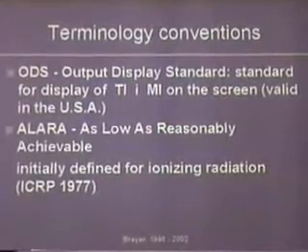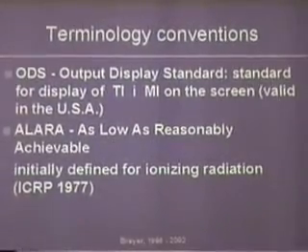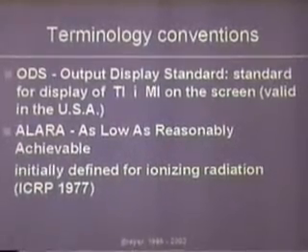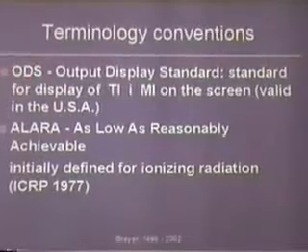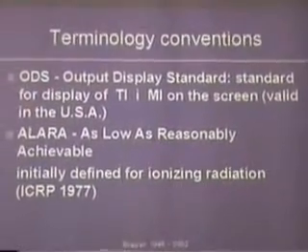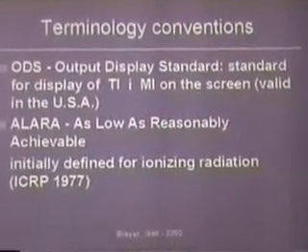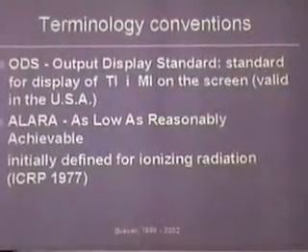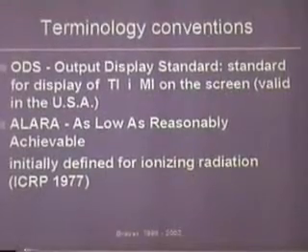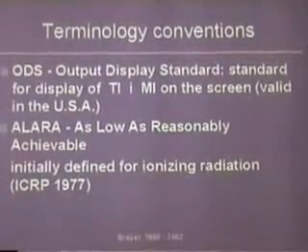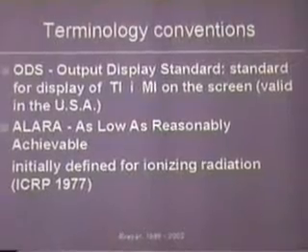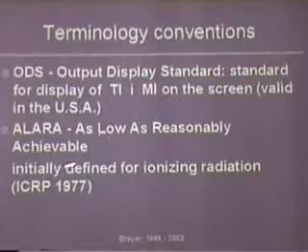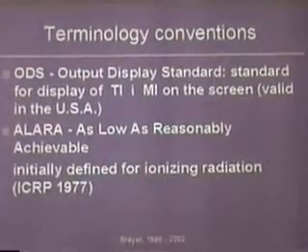Now, there are certain terminology conventions that you may not know, and that's important for us in these discussions. One is something called ODS, Output Display Standard. There are international and national standards that define what and how it should be displayed on the screen, so that we can compare machines. And there is this ALARA principle, which is just a normal common sense principle, which means that we should use hazardous agents, whatever they are, as low as reasonably achievable.